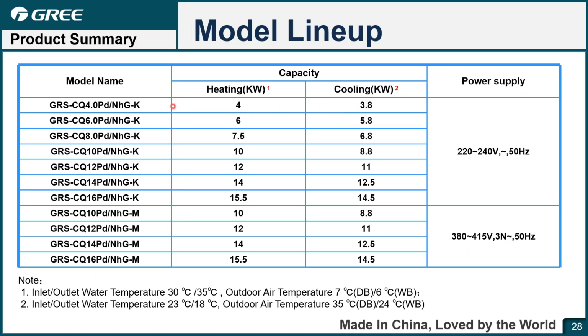And for the single phase, the power supply unit minimum is 4 kilowatts to 16 kilowatts. However, for the 3 phase monoblock VERSATI 3, the minimum is 10 kilowatts. Maximum is also 16 kilowatts. So actually, for the monoblock, the minimum 3 phase unit capacity is bigger than the split one and all-in-one type.